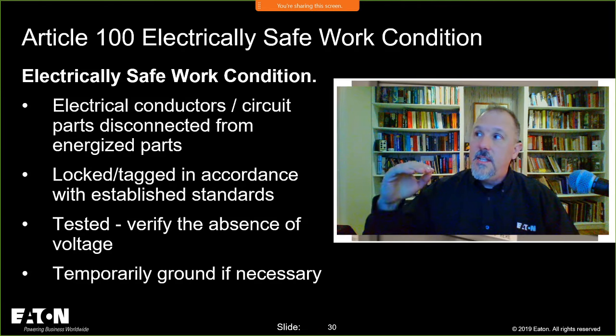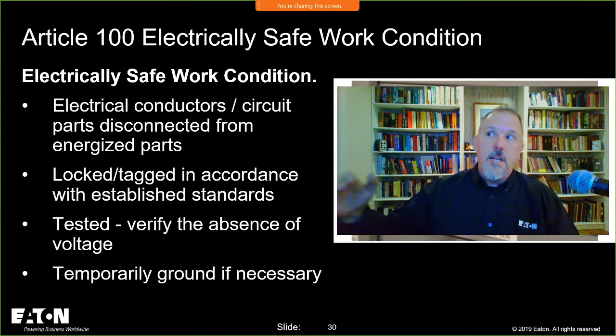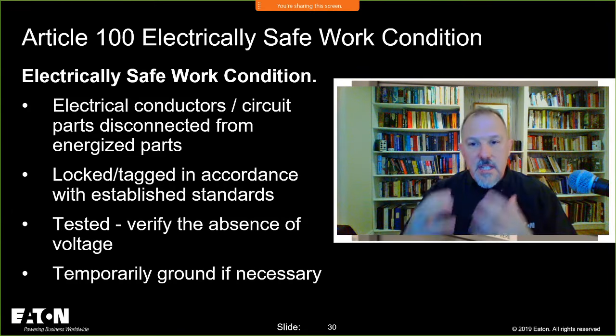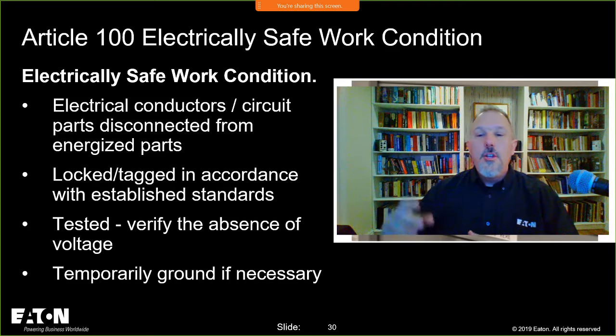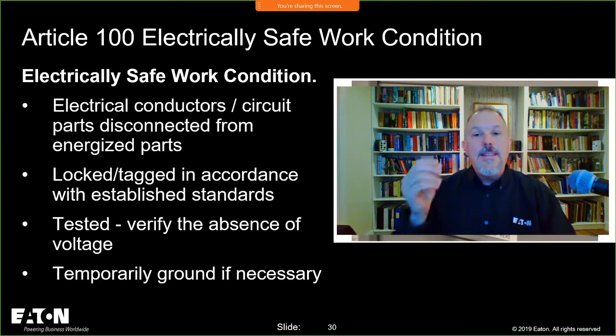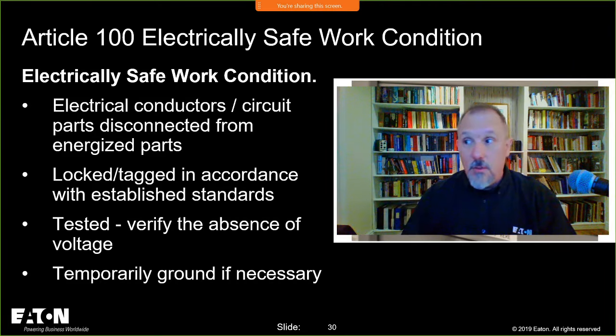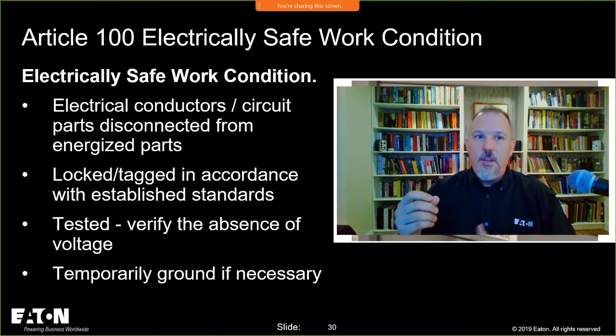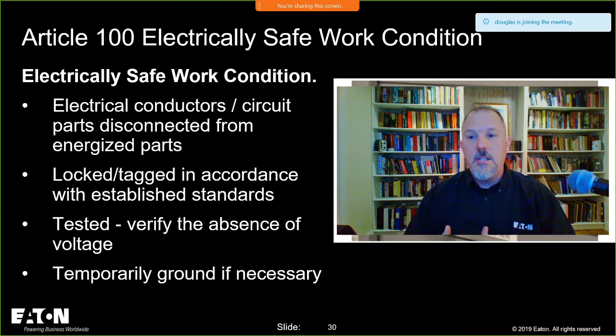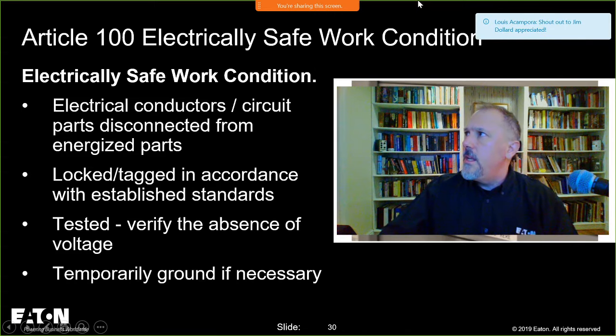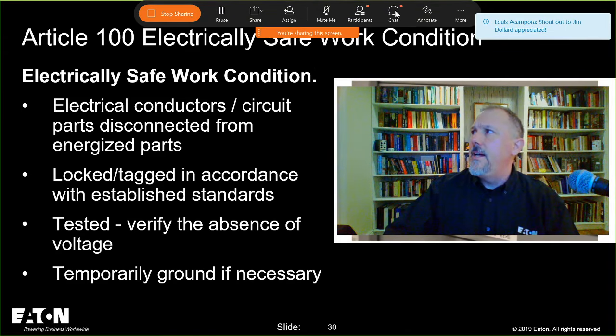The definition tells us that we have to put all of the electrical conductors and circuit parts, and you have to disconnect them from energized parts. You need to lock and tag things out. We need to test and verify absence of voltage, and you may, under certain conditions, have to establish a grounding for safety.